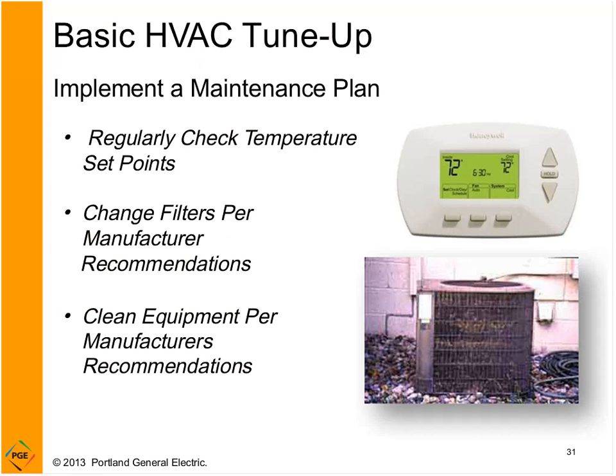So much like the lighting tune-up, we want to implement a maintenance plan. And part of our maintenance for HVAC is to look at our thermostats. You know, where do we have the temperatures set where we want them? Is the time programmed correctly? Things of that nature. And this isn't something that you can do once and then forget about it, because building occupants tend to make adjustments to these thermostats, even if they're behind a locked box, or if there's a code that you have to enter. You know, people are resourceful. They'll find ways to adjust things and maybe not have the systems operating at performance levels that you would prefer.